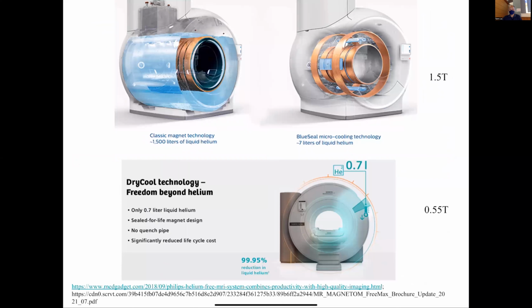So that's led to manufacturers trying to come up with designs that don't use as much helium. This is from Philips, where a classic technology that they would have might use 1,500 liters of liquid helium, okay? And I forget the price of this, but liquid helium is not cheap. You're talking about hundreds of thousands of dollars sometimes to buy liquid helium, okay? For this much liquid helium, it's probably more. So this one, by contrast, uses only 7 liters. Okay, so engineers over the last decade or so have come up with ways where, instead of using liquid helium, they just find ways of thermally conducting heat very quickly away and dissipating the heat so quickly that they need less helium.